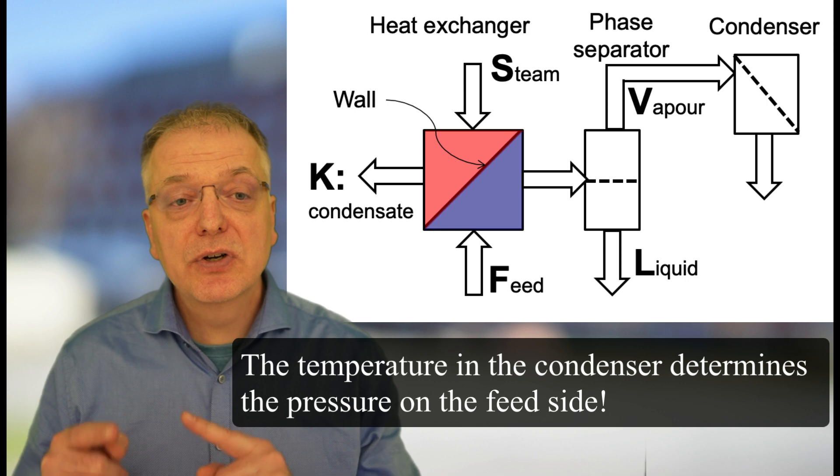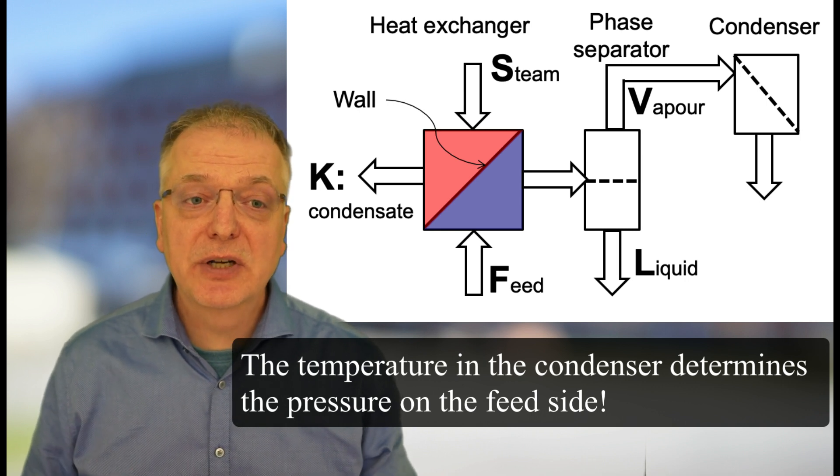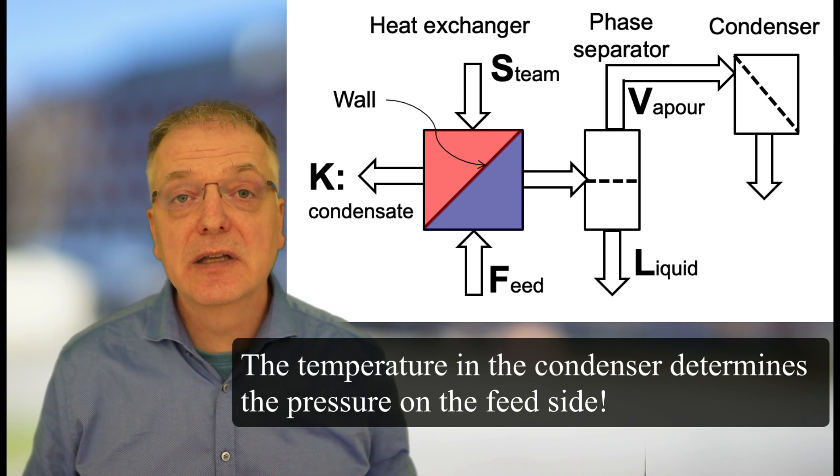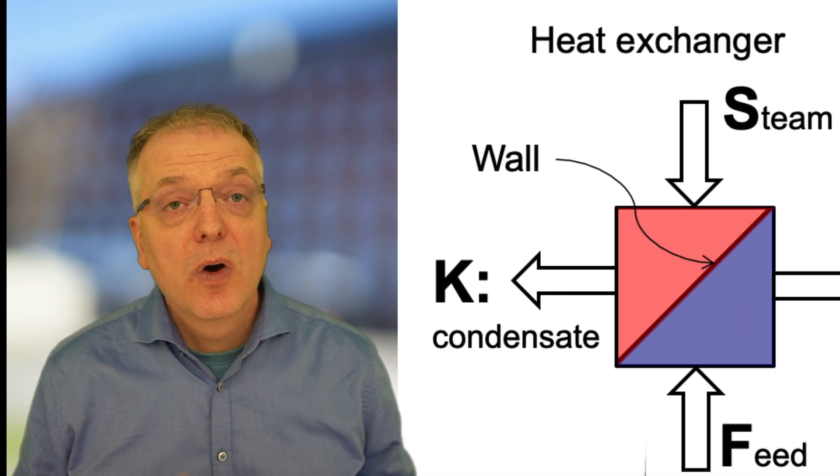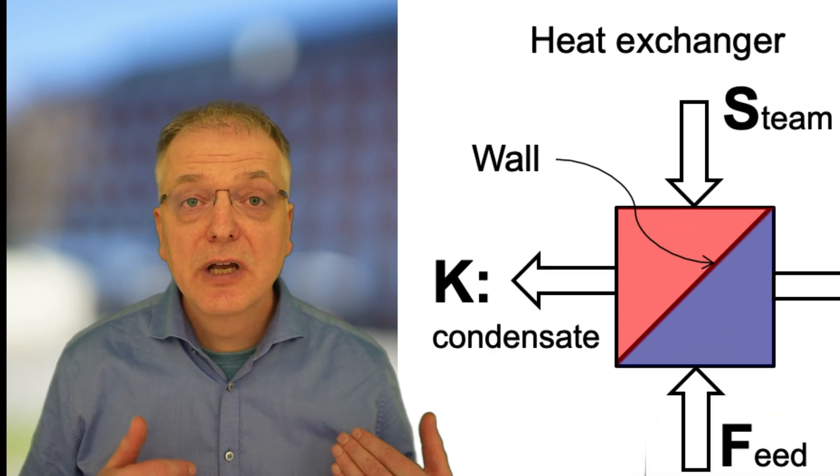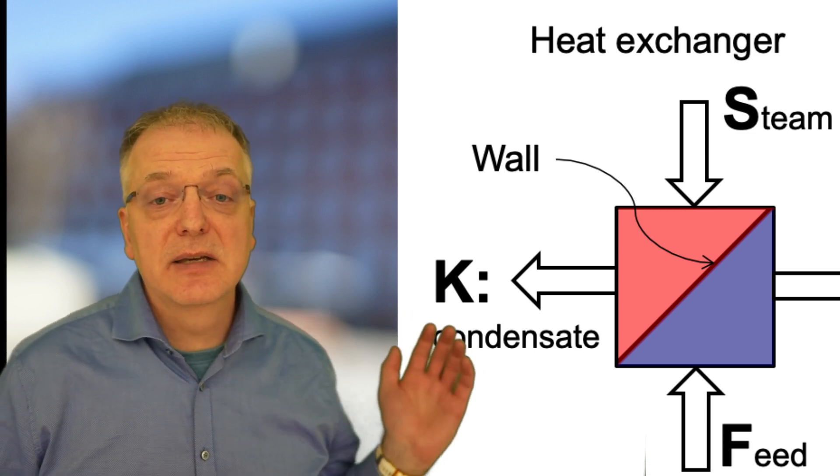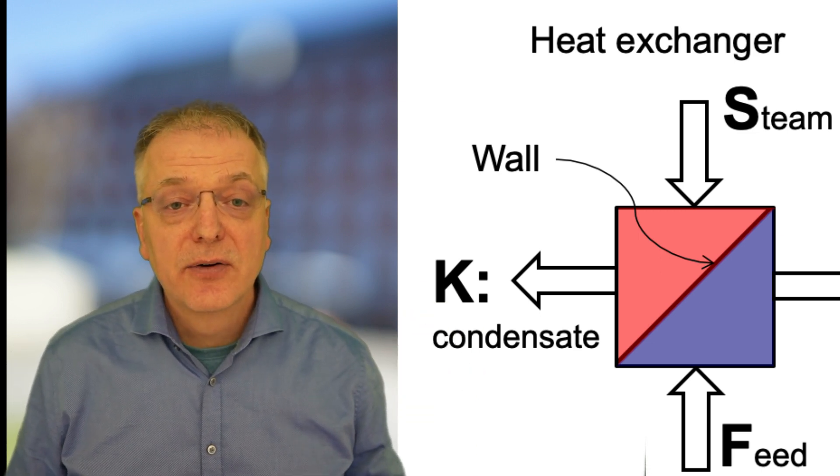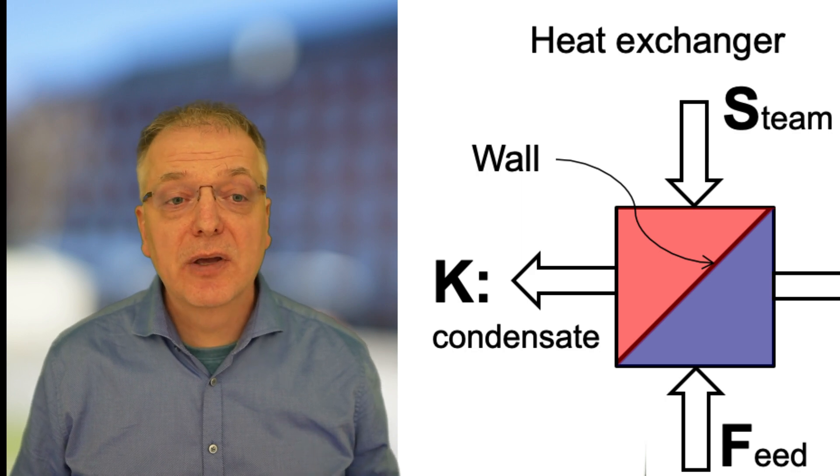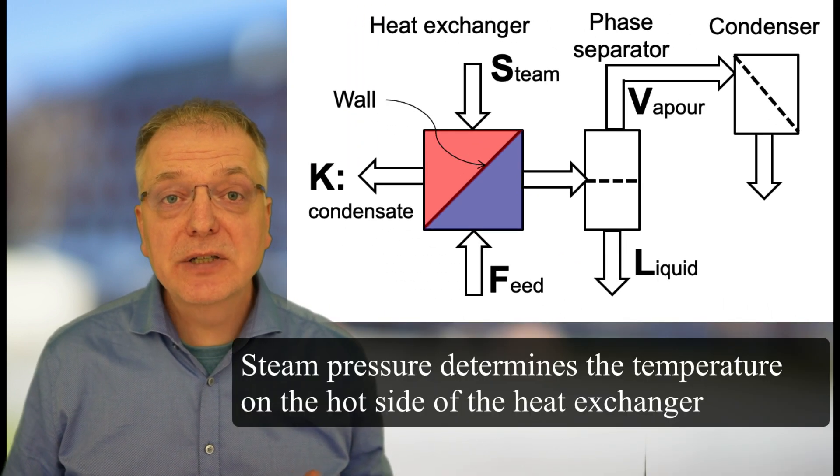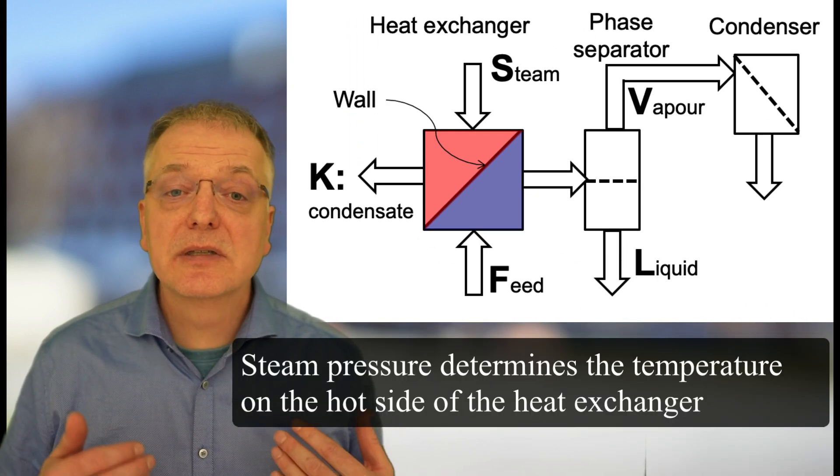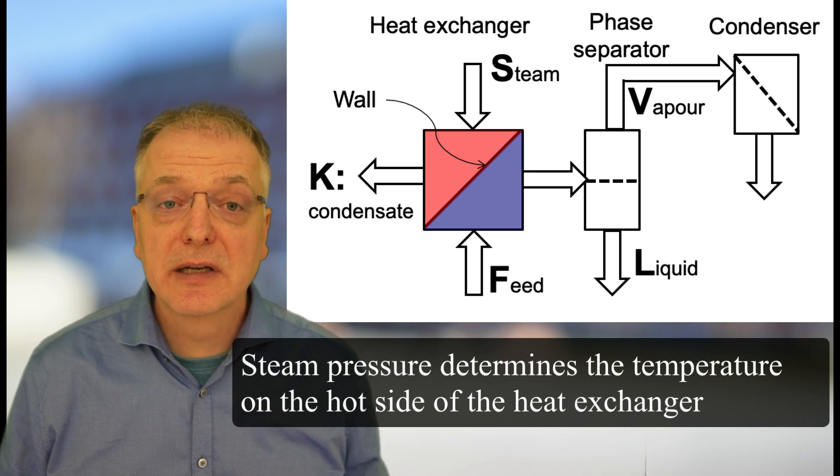It is the temperature in the condenser that determines the pressure of the feed side of the heat exchanger. On the hot side of the heat exchanger, we usually have condensing steam, S. That is, we take in steam and let that condense, releasing the evaporation enthalpy of the steam. The pressure of the steam determines the temperature on the hot side of the heat exchanger.